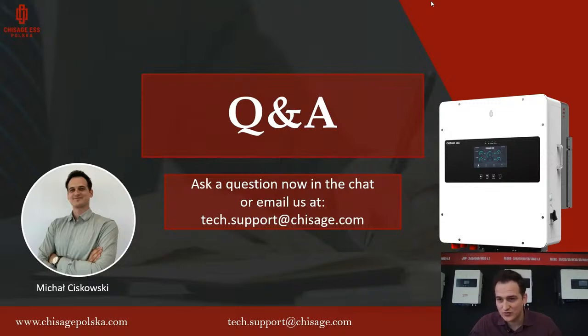If we set it to 170, are we losing warranty? Basically, the inverter will not give you permission to set less than it can be. For Mars it is 165 volts, and you cannot go lower than this. You cannot set settings lower than this, so you will not lose the warranty if the inverter approves these settings. That's okay.